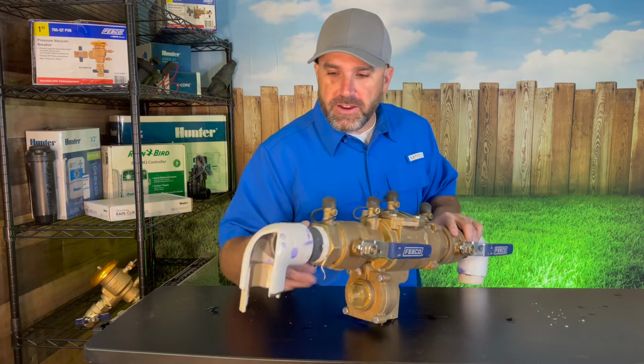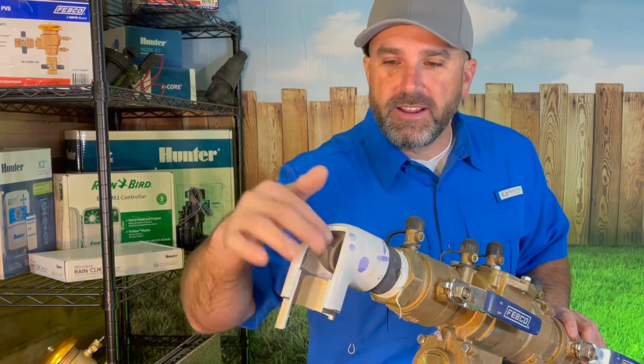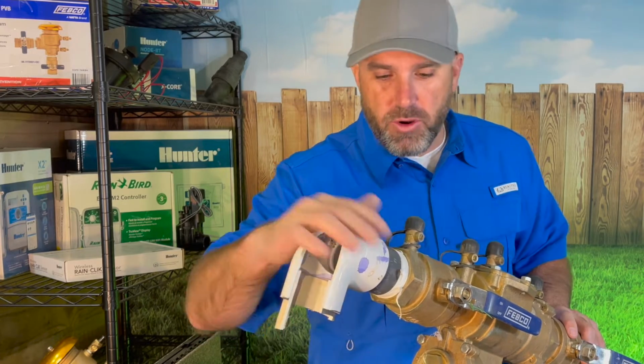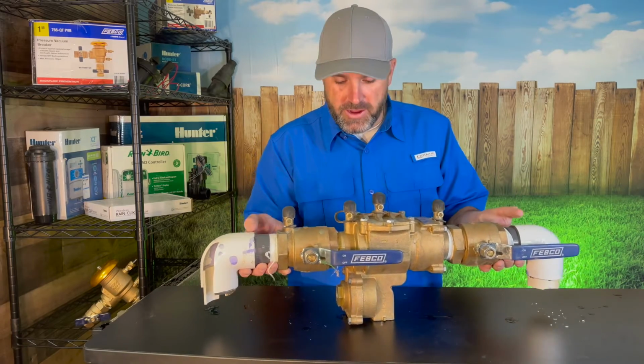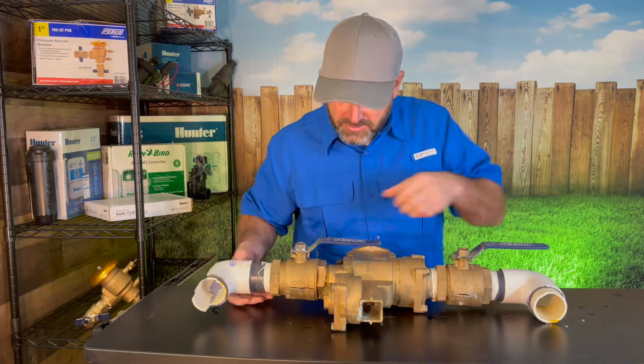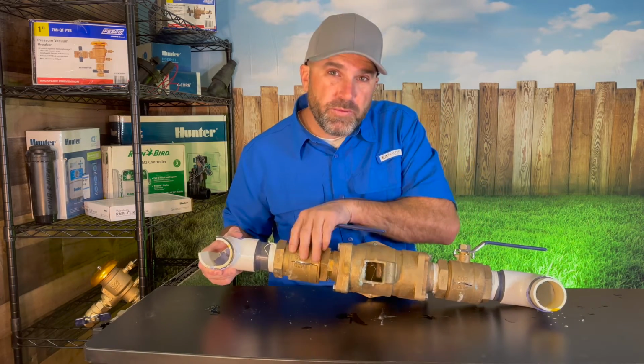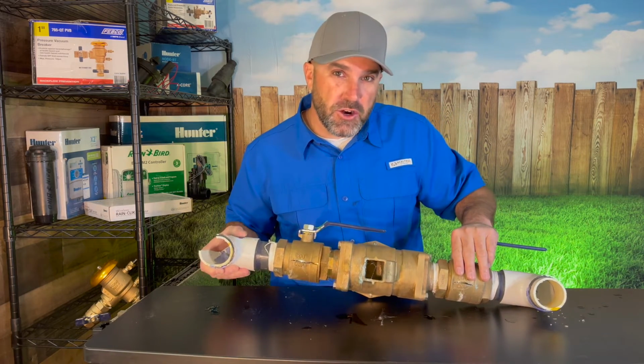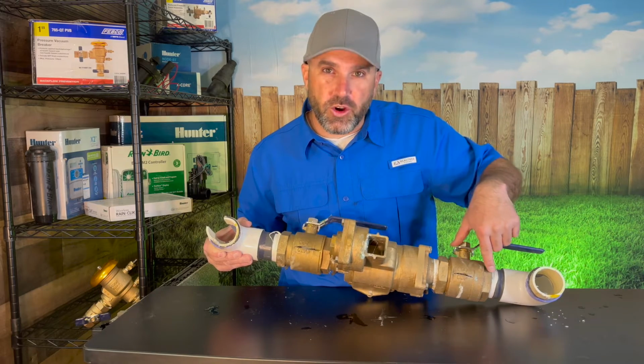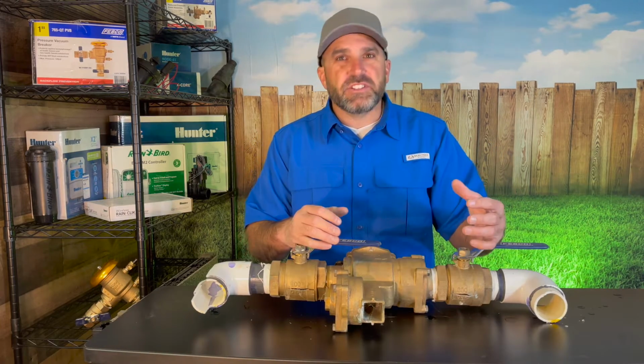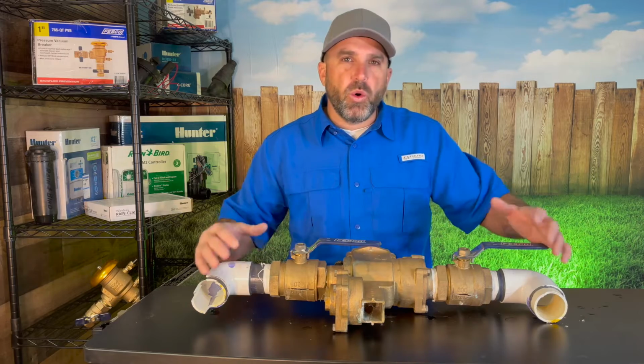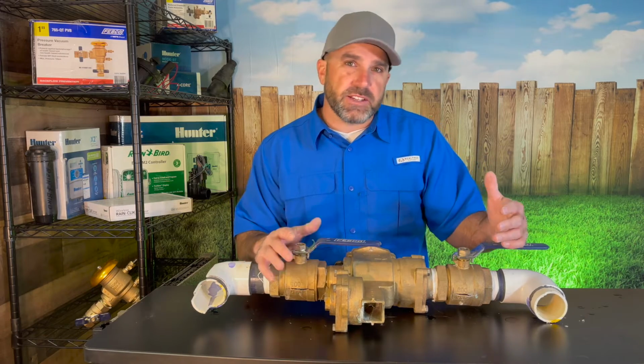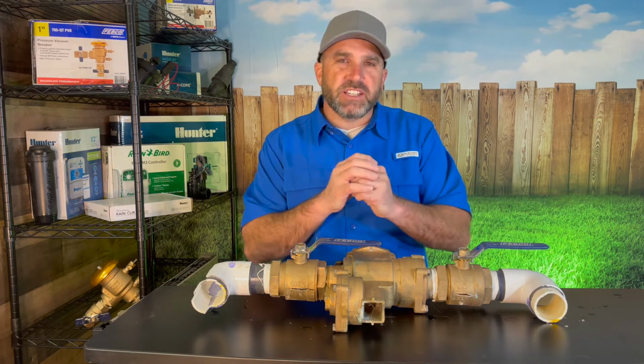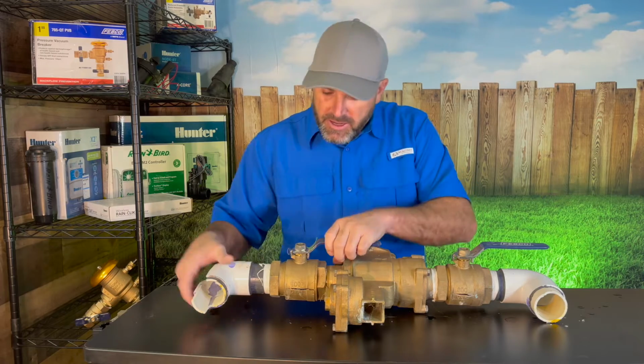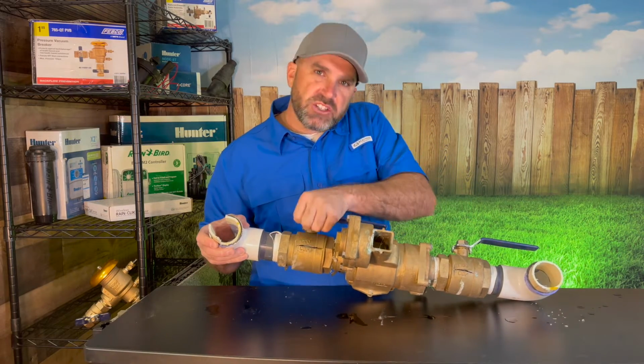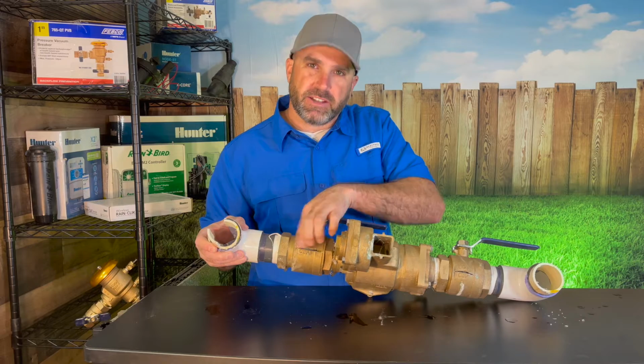You can see first right here, just regular PVC. This cracked and broke. Let me show you what else cracked. Both of the ball valves and shutoff valves of this RPZ froze and cracked. What happens is when water is full in a pipe or backflow device like this, when it freezes, it'll actually expand. And that's what causes this to actually blow out and crack like that.